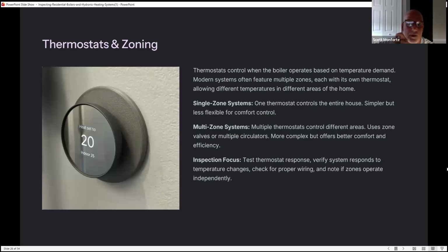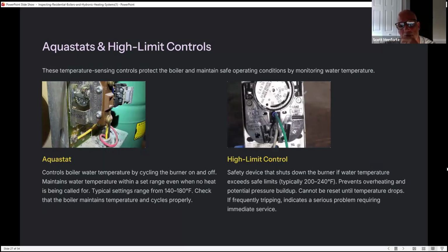So in other words, if you want to turn the second floor on and you're in heat, and just say you're checking the heat, you let it cool down, and you switch over to AC, you got to go back down and make sure that downstairs is on cool. It may not. You'll sit there trying to turn it on and it's not going on. So just keep that in mind with multi-zones.